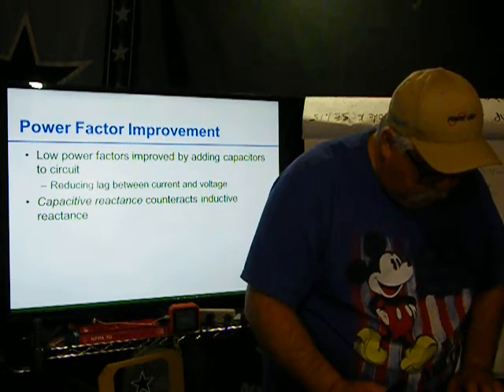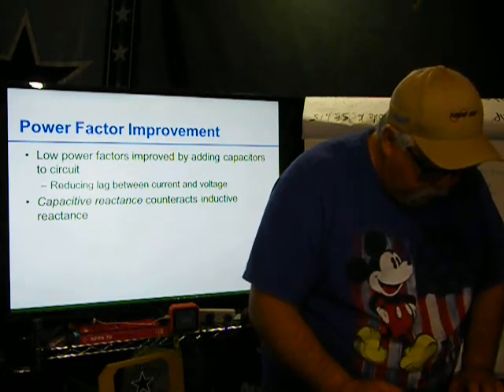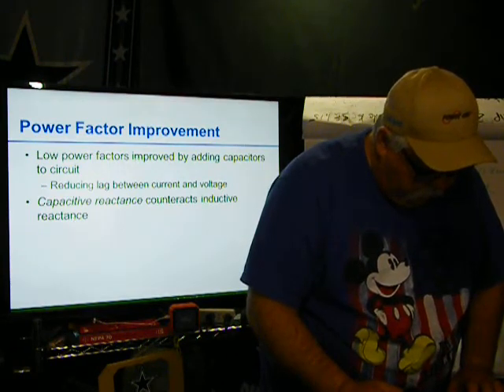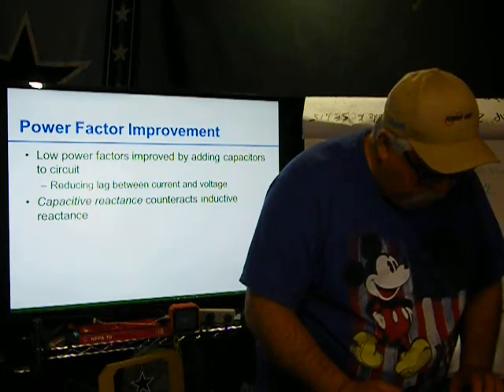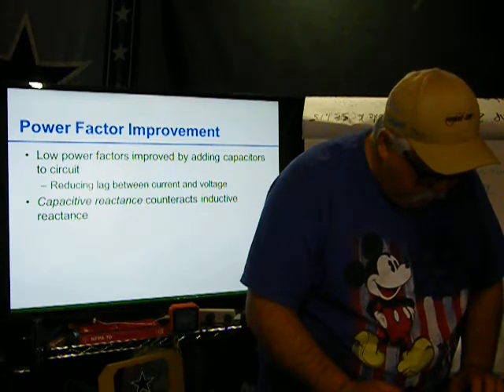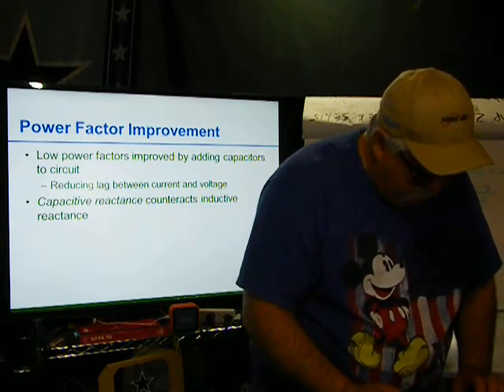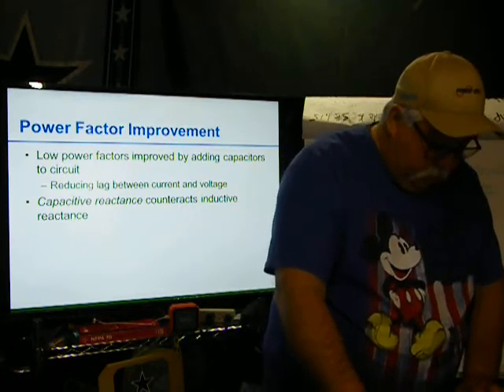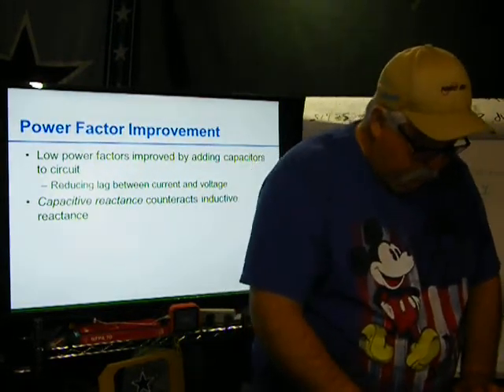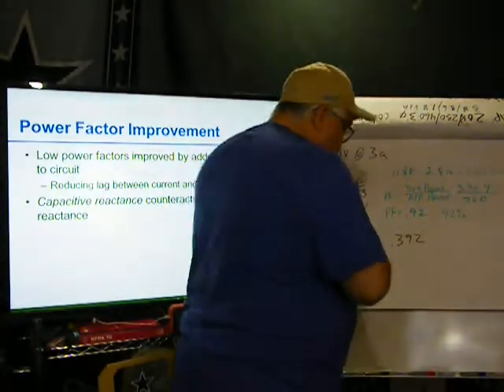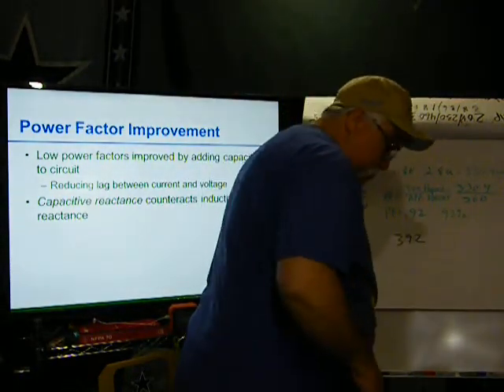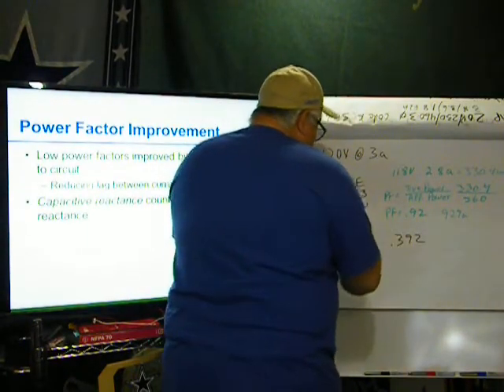It says a sample problem says a 55 horsepower three-phase motor, full load current of 65 amps at 460 volts, a power factor of 65%. What size capacitance is needed to raise the power factor to 90%? So I'm going to get the, let me write it on here. So it's, yeah, the true power, I'm sorry.